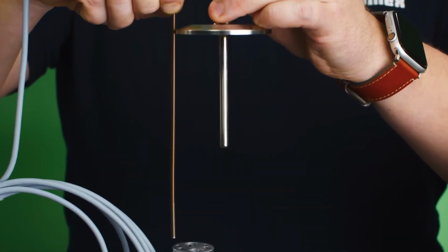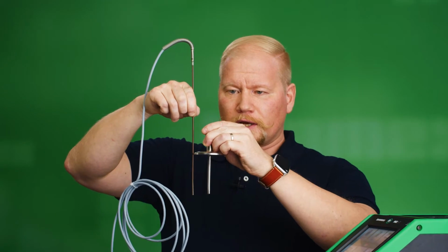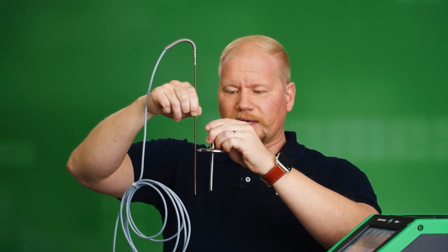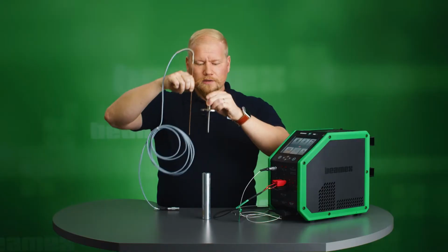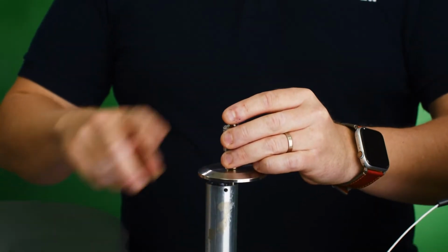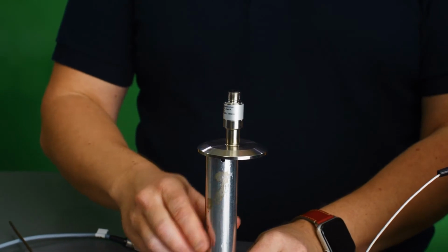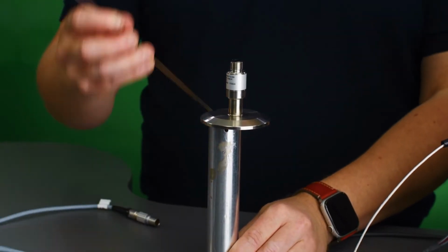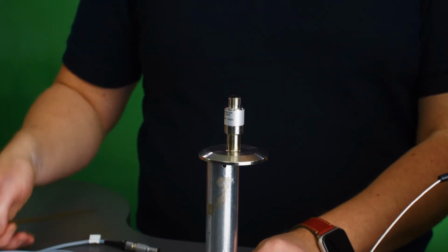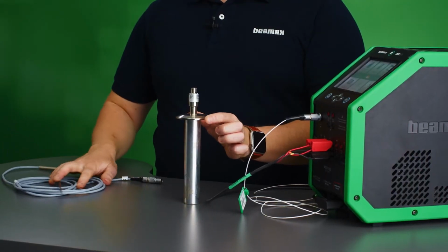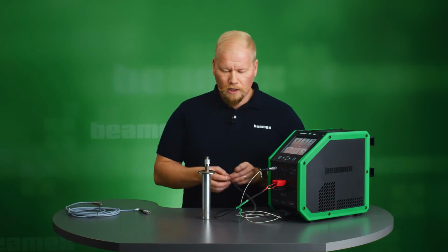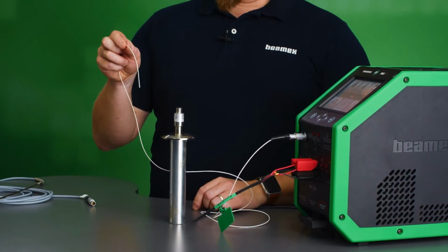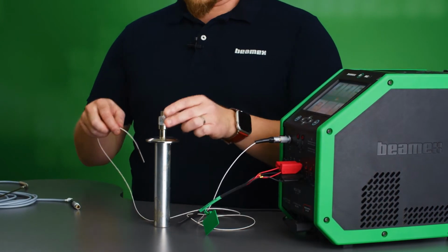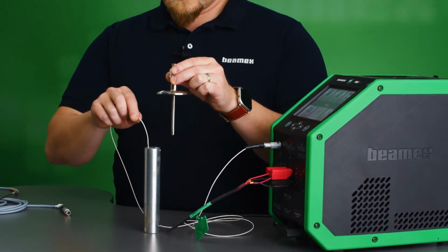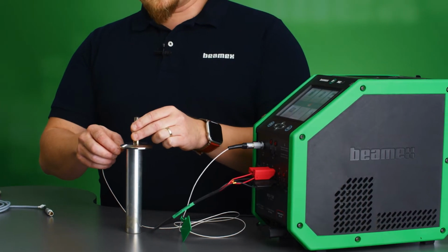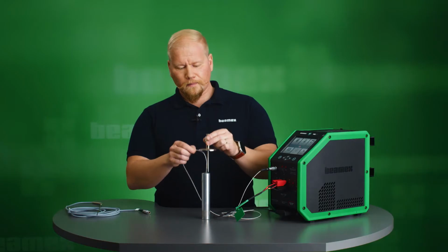I need to have my reference at the same depth as the sensor that is being calibrated, and preferably as close to it as possible. So now when I place my short sensor on the insert, this one also has quite a big flange. It's covering all the other holes, so I cannot use this as a reference. To solve this, I need to use a short reference sensor with a flexible cable. So now I could use this, place it here, but the problem is I don't know what the depth is.